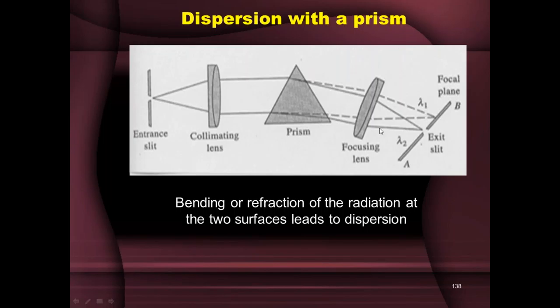Lambda 2 exits out of the monochromator through the exit slit. Lambda 1's focal point falls at some point on the focal plane but not on the exit slit, so it gets lost. Out of the two wavelengths lambda 1 and lambda 2 entering the monochromator, only lambda 2 exits and is incident on the sample. Bending or refraction of radiation at the two surfaces of a prism leads to dispersion — this is how monochromatic radiation is obtained using a prism.